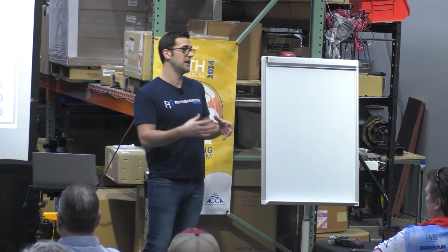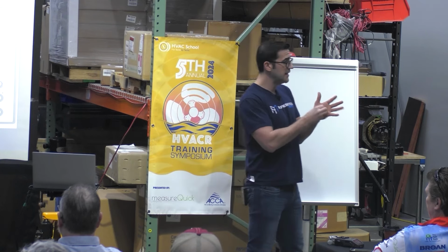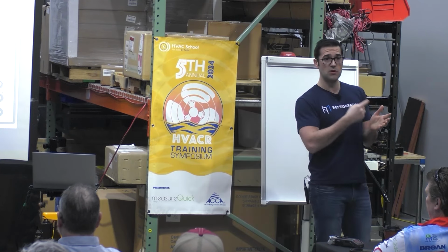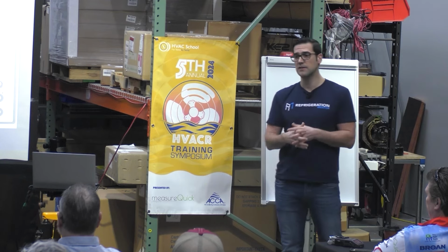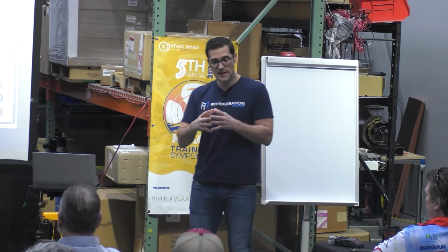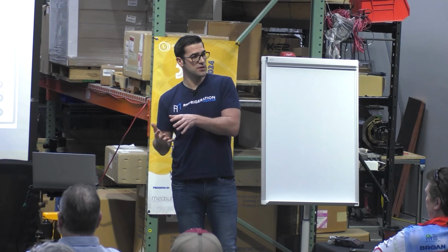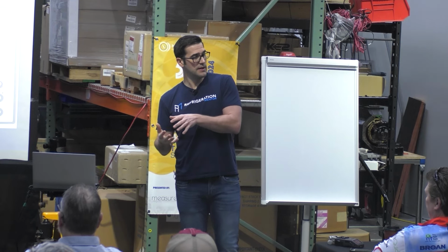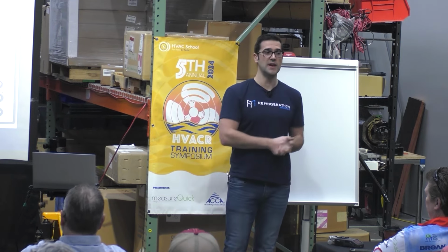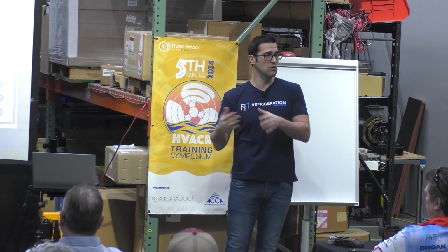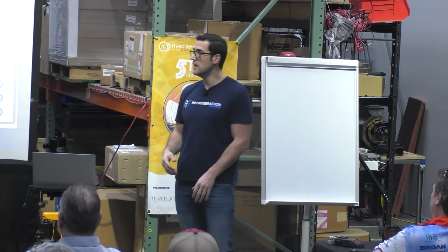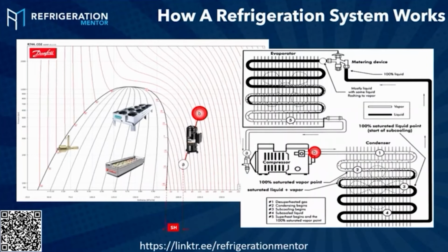That compressor has a stator and a rotor in it. And when that energy hits that compressor, it starts to rotate. There's a magnetic field and there's a whole process behind it. But just think, it's taking low temperature refrigerant vapor and compressing it to high temperature vapor. That's what we're doing. Low temperature vapor into high temperature vapor. So it brings us up, and this is our heat index right here. These red lines are all the different types of heat. So you've got motor heat, you've got compression heat.